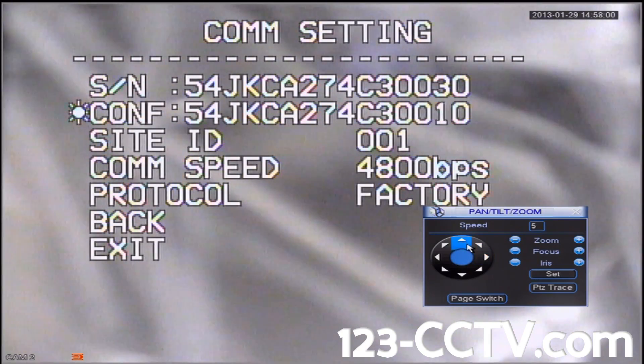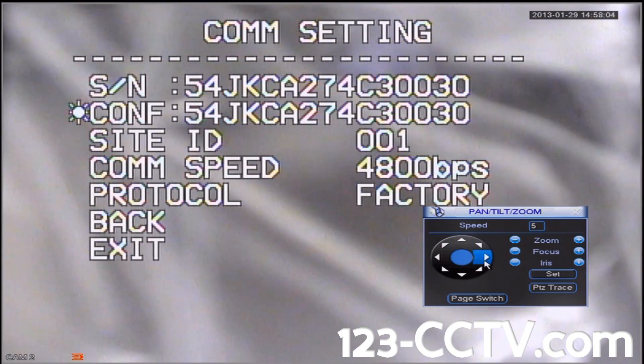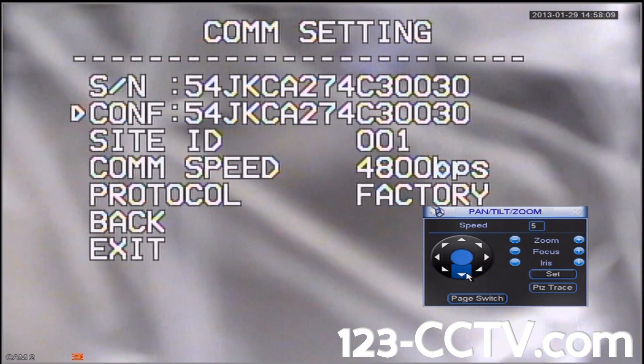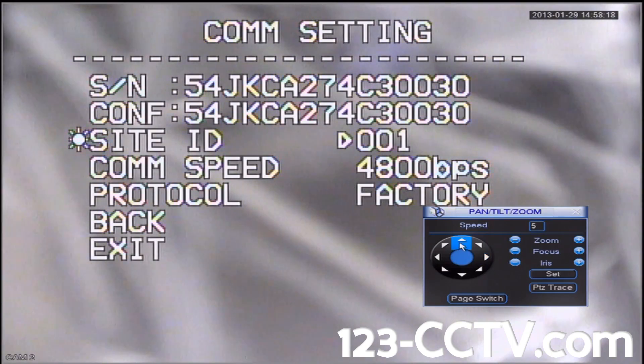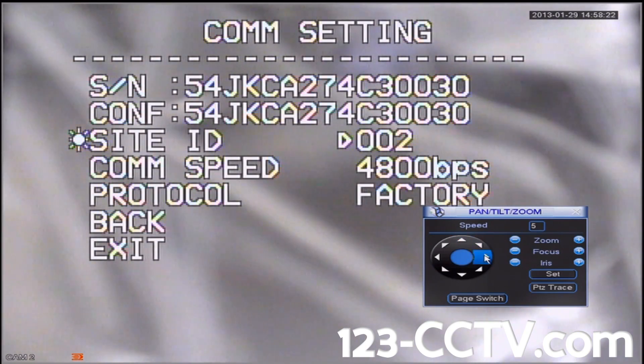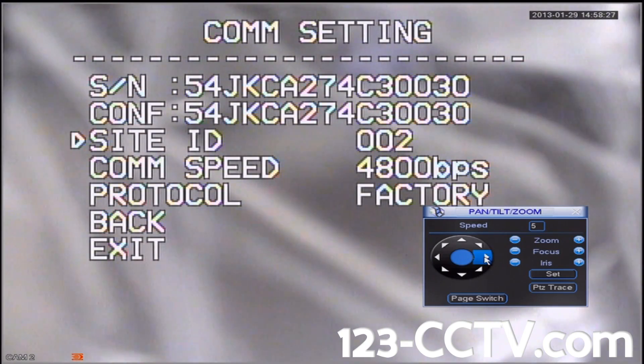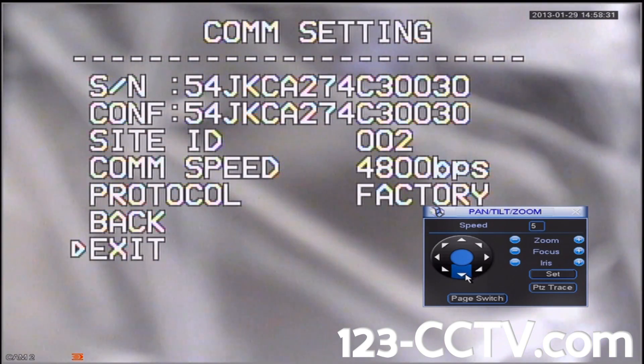Once you have duplicated the serial number in the confirmation line, press Right to exit out of the confirmation line. Then press Down to go to Site ID, press Right to select, and change the site ID to the correct address. In this case, it's on Channel 2, so we're going to select site ID number 2. Press Right to select, then scroll down to Exit and press Right to exit.